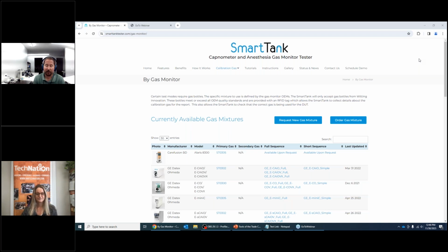So what we ask our customers, if they want a new sequence written that we don't have, again, it's free, but we ask them for two things. We ask them to help us find a service manual, because sometimes those are very hard to find, as I'm sure everybody knows. And you probably have them if you're doing those PMs. And then the second thing is, once we write the sequence, please just bear with us, test it out, and report back on whether or not there's any issues with it. We don't have all of these devices in our shop, so we will write it based off the service manual and then work with the customer to tweak it and smooth it out and make sure that there's no authoring issues, like we didn't write it wrong or missed something. And then once it's good, you're good to go, and then we make that available on our website.